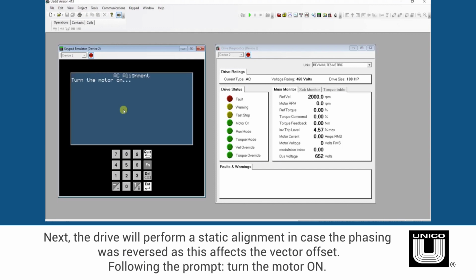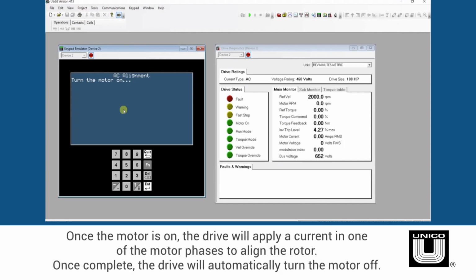Next, the drive will perform a static alignment in case the phasing was reversed, as this affects the vector offset. Once the motor is on, the drive will apply a current in one of the motor phases to align the rotor. The drive will use ID amps unless the entered value was less than 1/3 of the motor rated current. In this case, the drive is using 1/3 of the motor rated current, as this is larger than 10 amps.